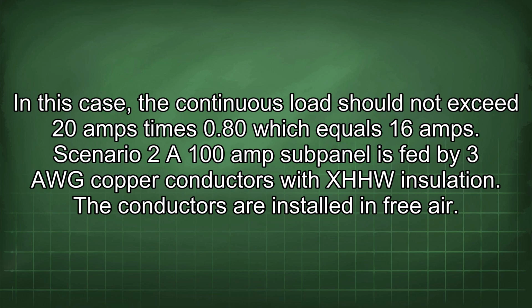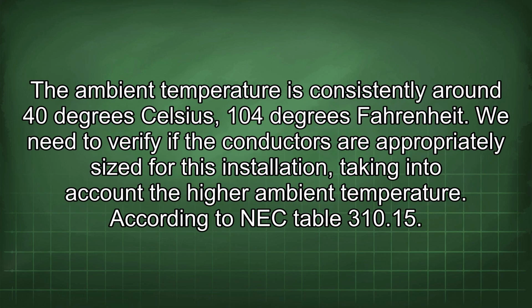Scenario 2, a 100 amp subpanel is fed by 3 AWG copper conductors with XHHW insulation. The conductors are installed in free air. The ambient temperature is consistently around 40 degrees Celsius, 104 degrees Fahrenheit. We need to verify if the conductors are appropriately sized for this installation, taking into account the higher ambient temperature.